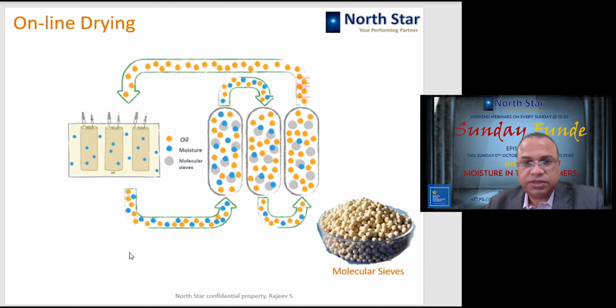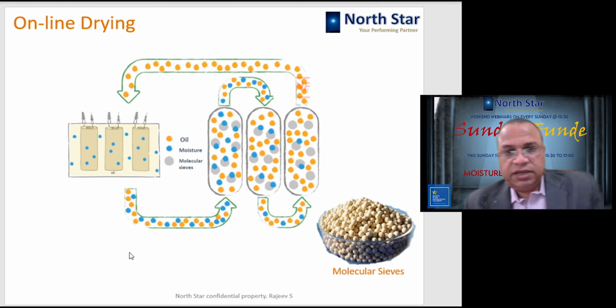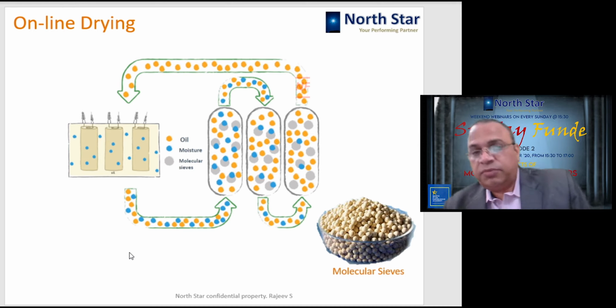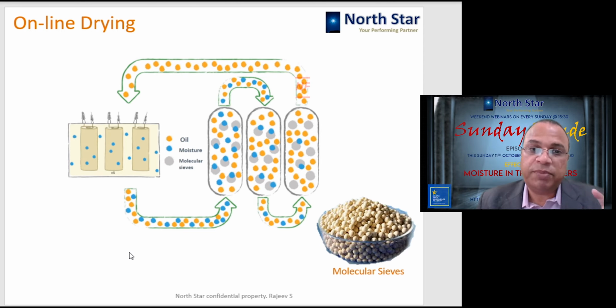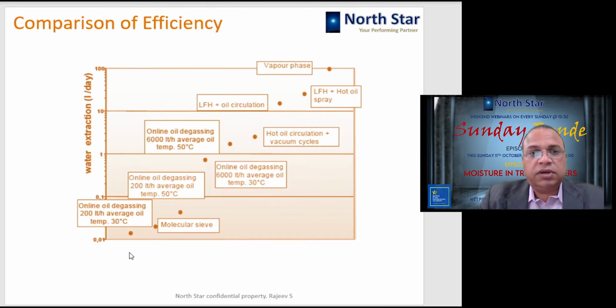Of course, it is a slow process, so it cannot be used for quick drying of the transformer. Where there is no emergency and you want to remove the moisture from the oil permanently, this is the ideal system, which can be easily integrated into your working transformer. Okay, so let us see the comparison of efficiency. There are several methods. We have seen online filtration methods, then LFH plus oil circulation, vapor phase drying, and molecular sieve.